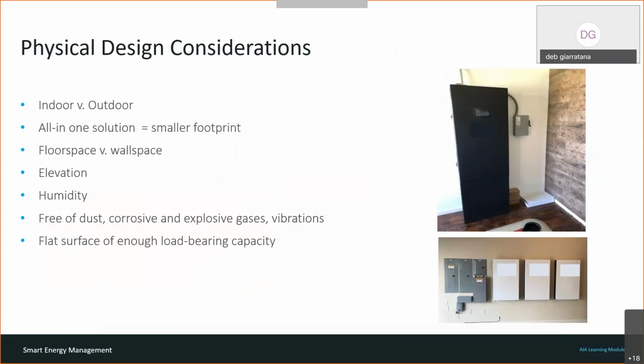What's the elevation? It actually makes a big difference if you're in Colorado and have to account for that elevation. If you're in the mountains or at sea level, it actually changes your design. Is there humidity? Let's say you're in Florida, we are. Putting a unit in the garage might not be the best choice because it needs to be a conditioned space, free of dust, corrosive and explosive gases, and vibration. It can't be right next to a railroad or continually moving. And it has to be a flat surface, and it has to be load bearing because you've got pretty heavy batteries.